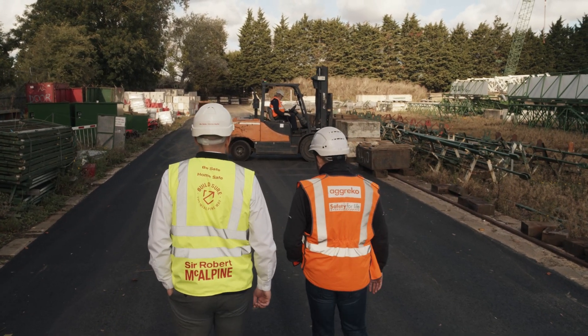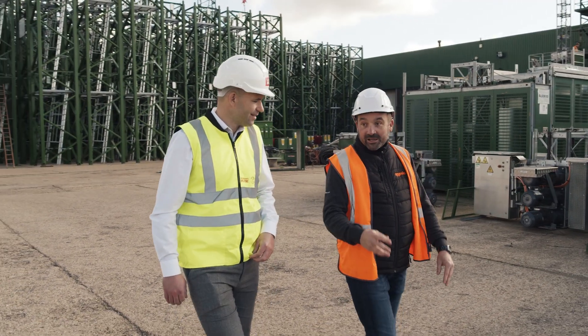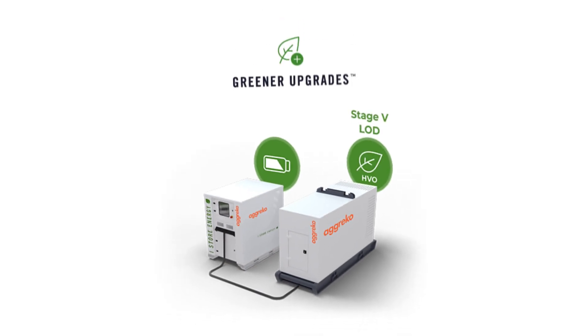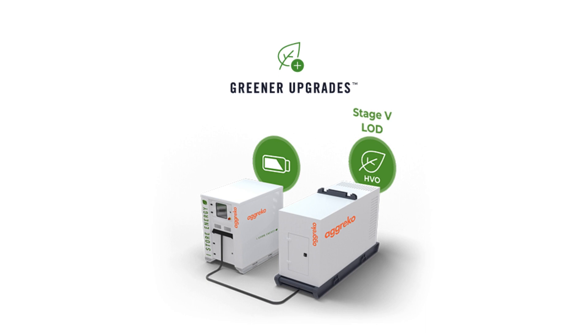We operated on site here for approximately two weeks, doing several tests on TC3 and TC4. We were then able to downsize the generators by incorporating a combination of load on demand packages which are run on HVO fuels and either hybrid batteries or flywheel technology.